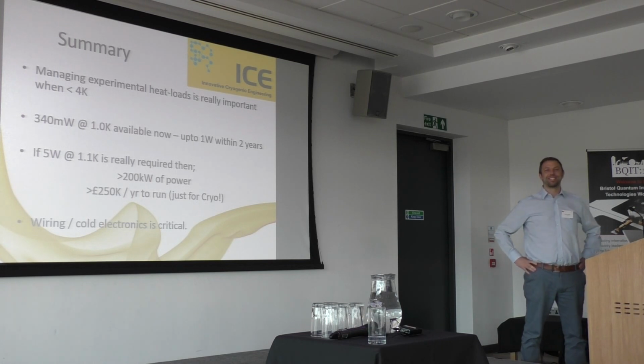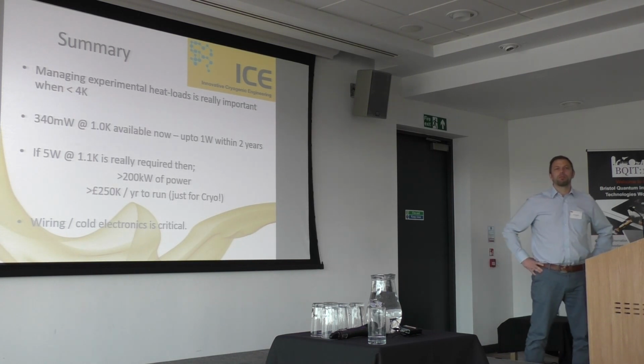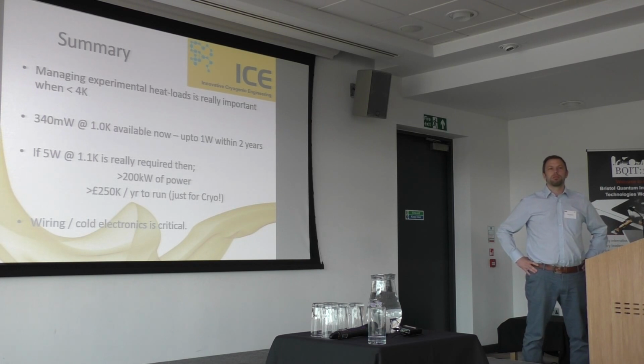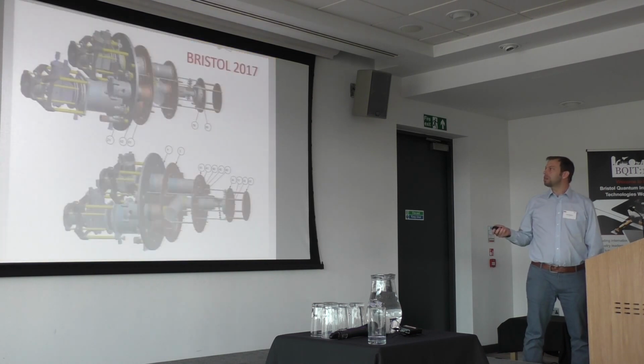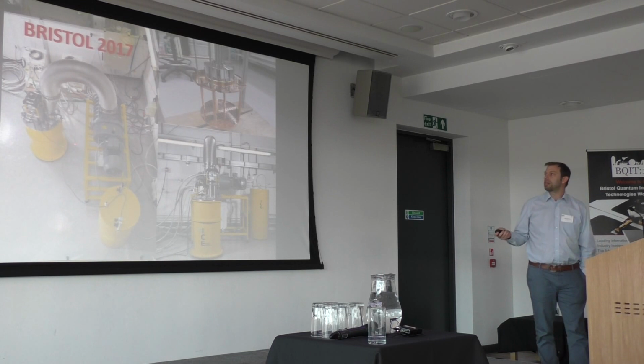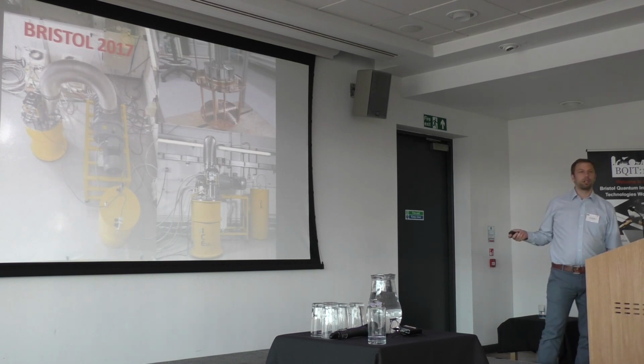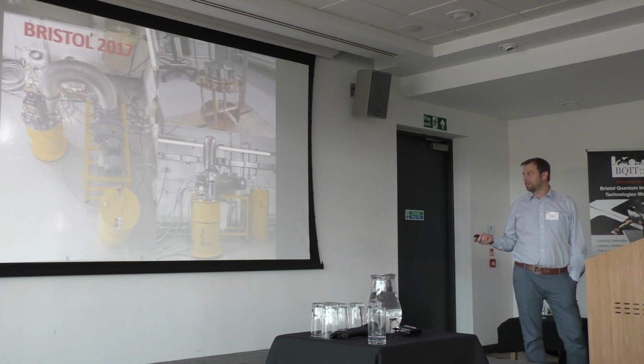Just wondering, in terms of vibration, you mentioned that there's a drawback of using dry pumps, the vibration. Have you come across some mitigation scheme or how much vibration do you measure? Well, there's 2 main sources of vibration on the system. One is the mechanical cold heads, which are producing around 20 microns of vibration mechanically, and that's pretty much linked directly in. What we've done here is we've put a set of bellows in to isolate the cold head from the cryostat, which brings the vibration down to sort of the 4 to 5 micron level.